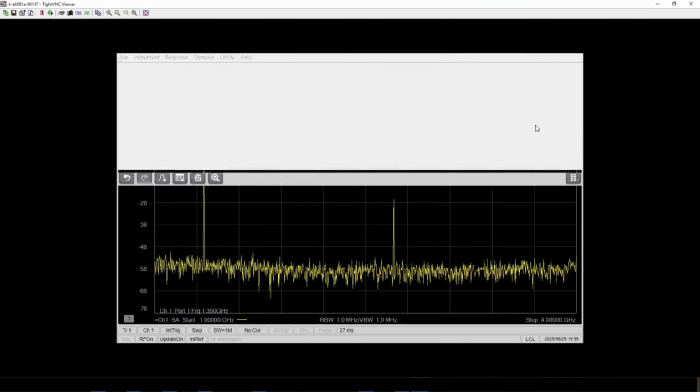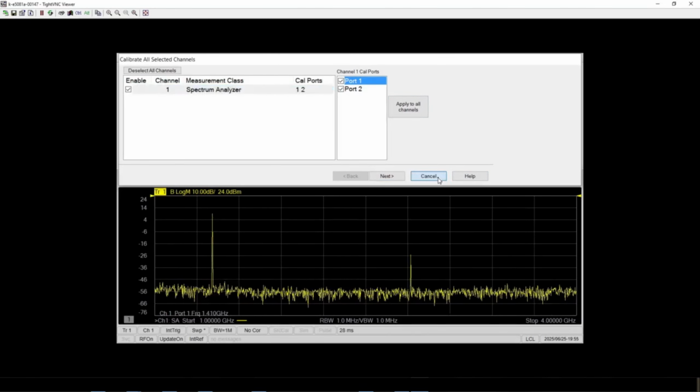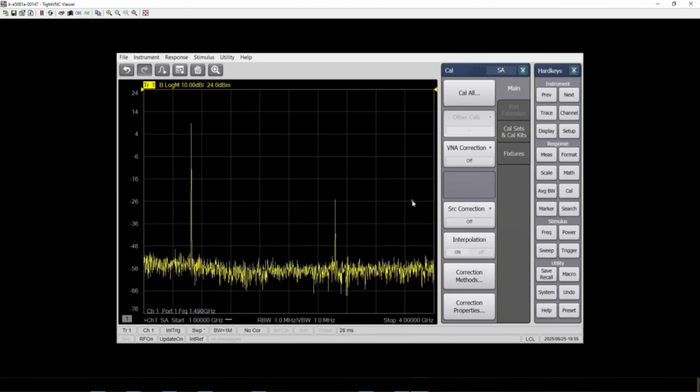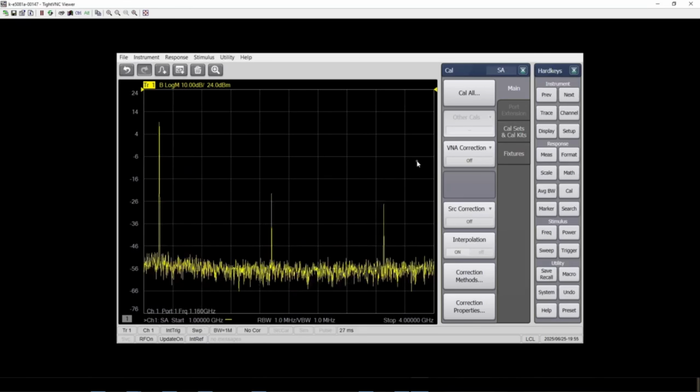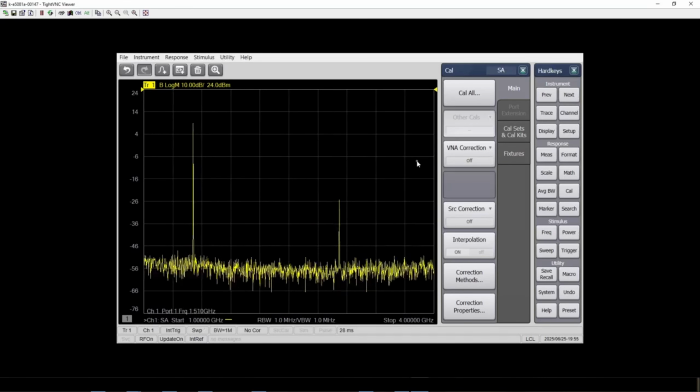So calibration is really just to make sure that the power from port 1 and port 2 are calibrated correctly, and your jumper cable is taken care of, still using the e-cal or mechanical cal.